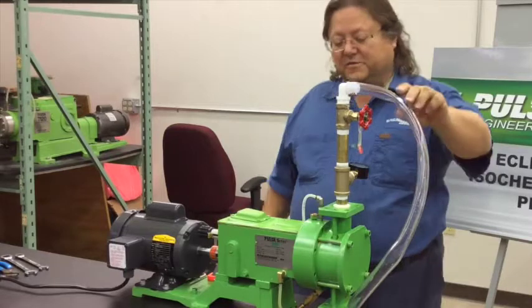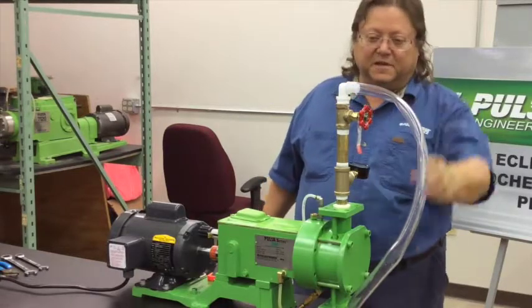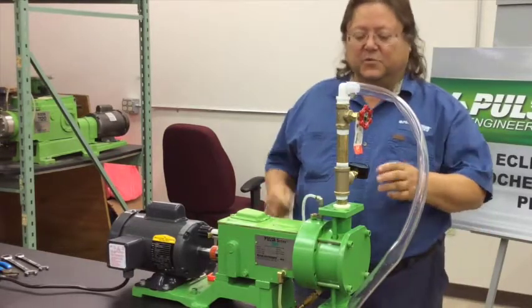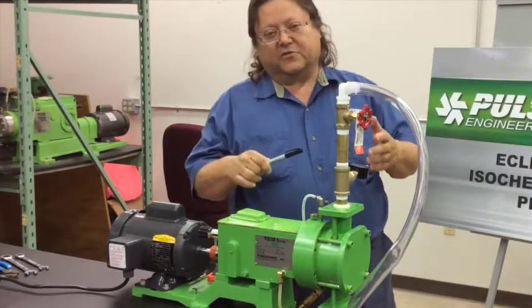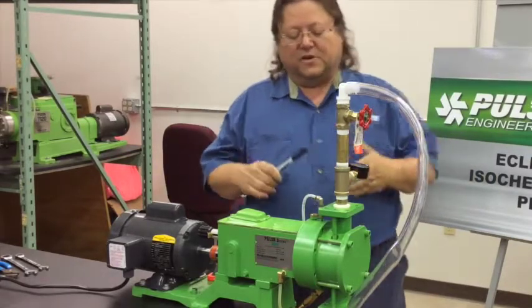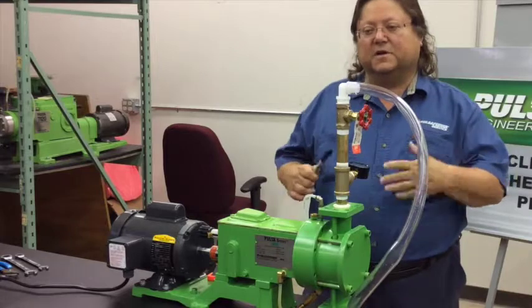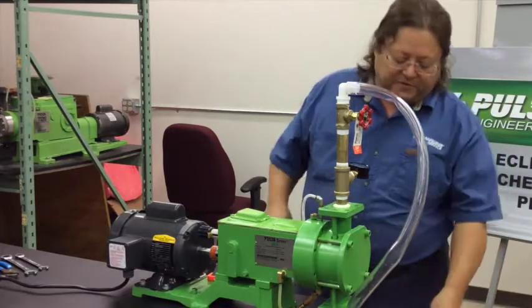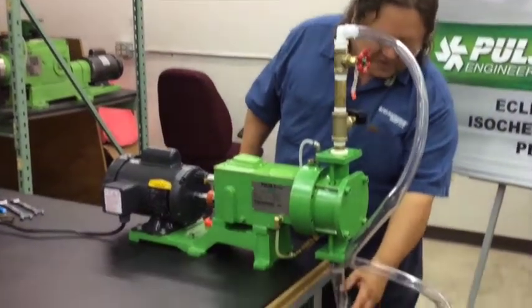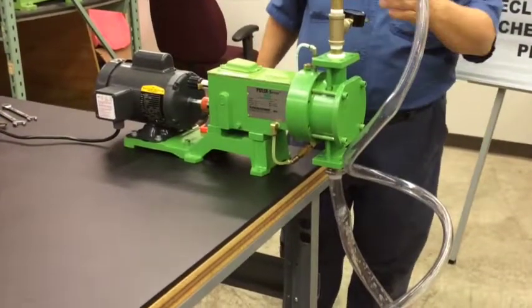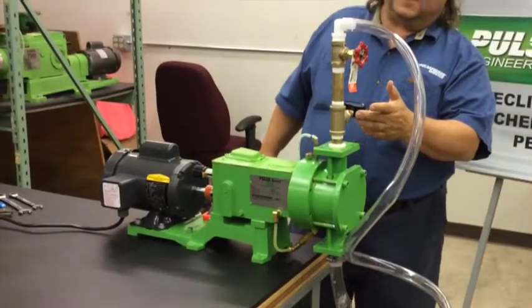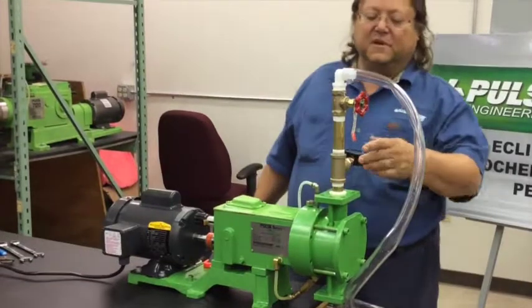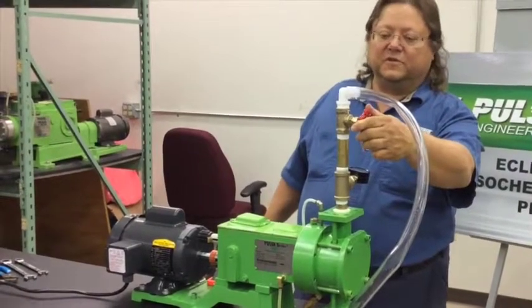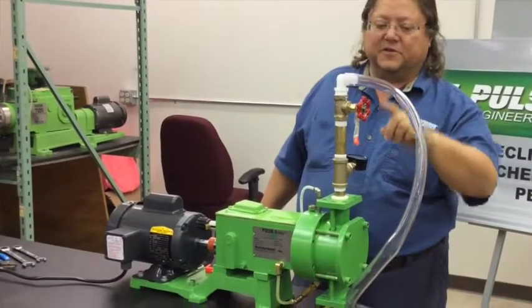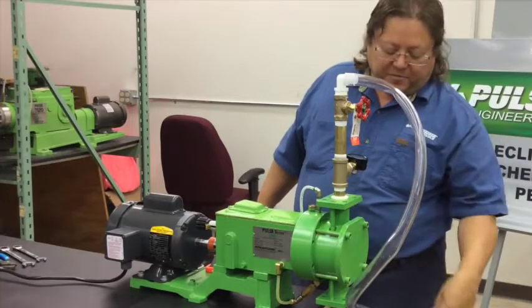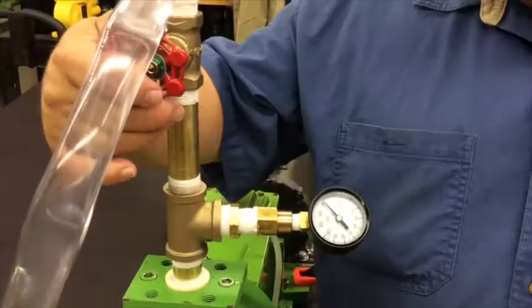What we've done here is we've added some piping to simulate the actual process. We need to be able to create some back pressure on the check valves in order to get that diaphragm to fully work efficiently. We've connected up some clear tubing here to the suction side. We've got a gauge here to indicate the back pressure on the system. I've got a simple gate valve that I'm using for adjusting the back pressure. And then we're just recirculating back into this bucket here of water.